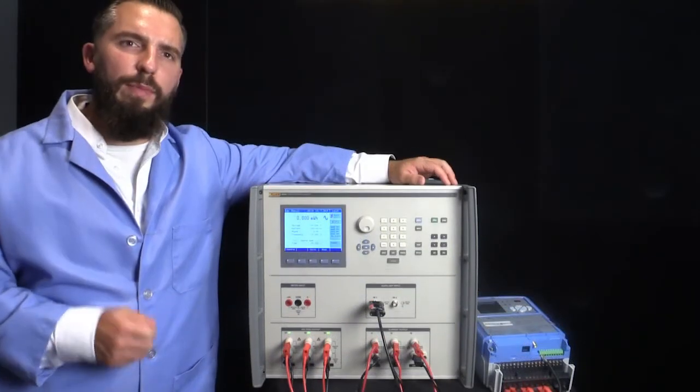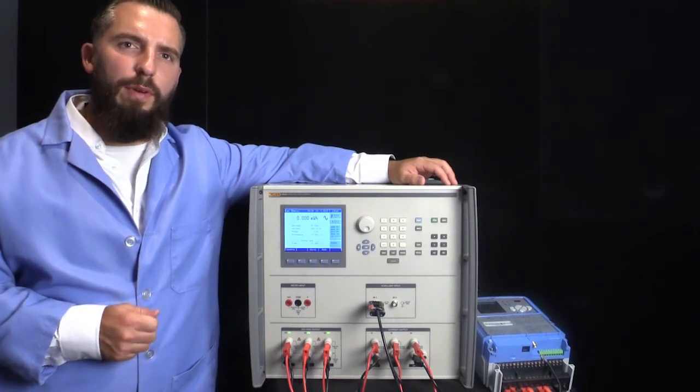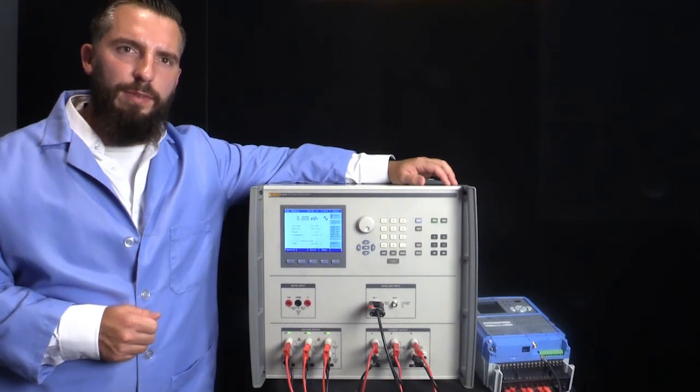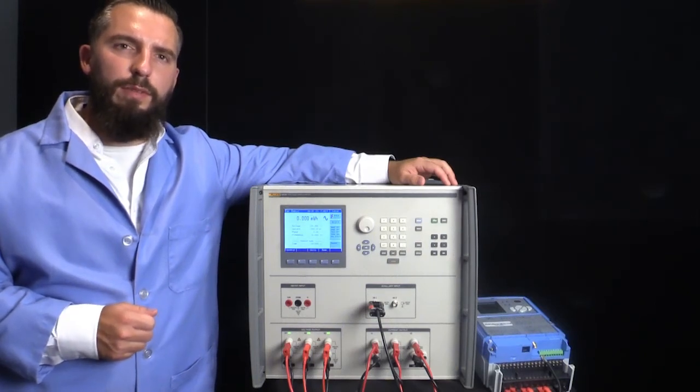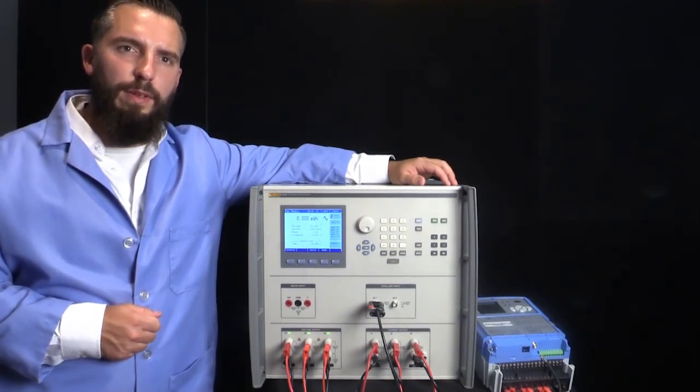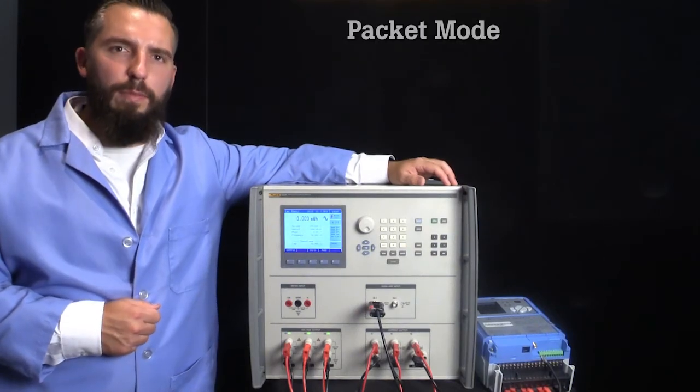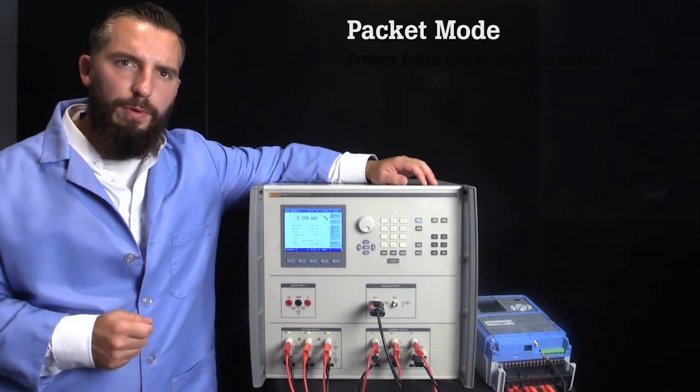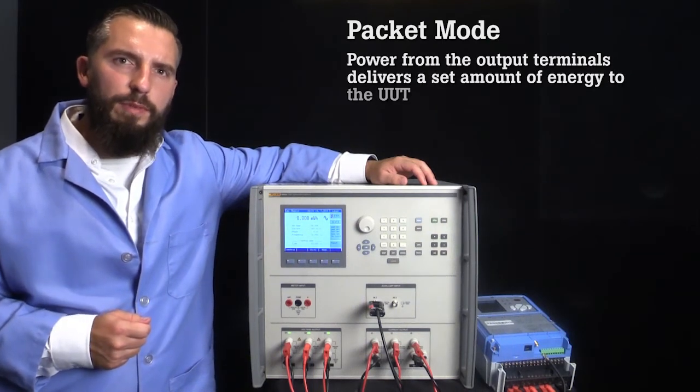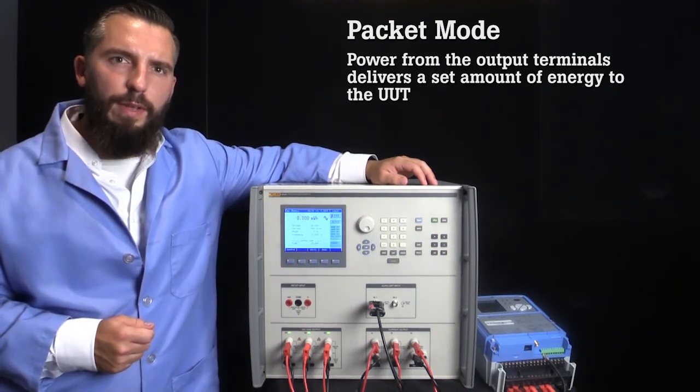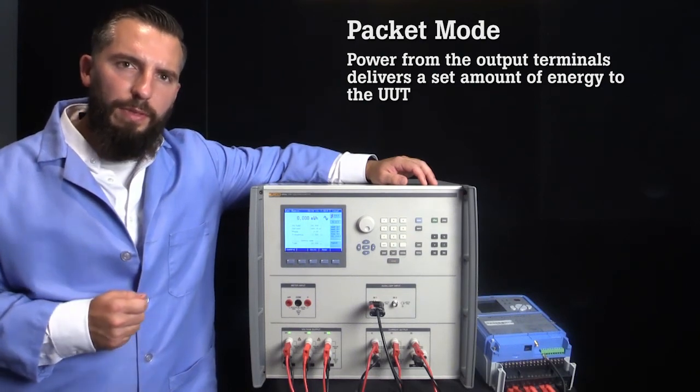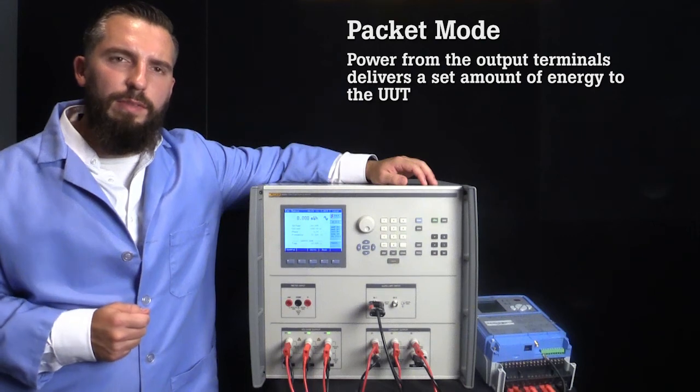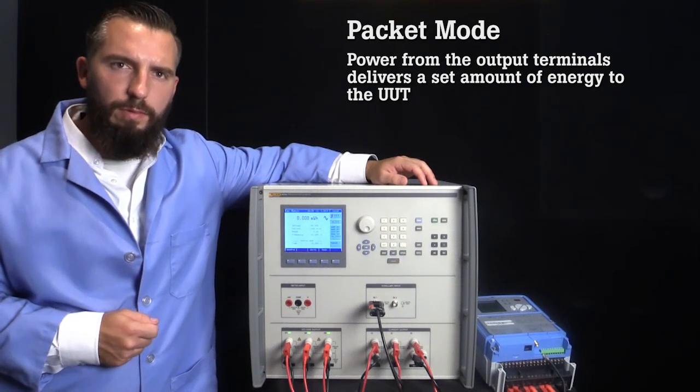In some cases, you may have to test an energy meter without a pulse output. In this case, the simplest method is to do a timed energy test where you compare the expected value to the measured value on the energy meter. This can be done using the packet mode. In packet mode, which is also known as dose mode, the power from the output terminals is timed to deliver a set amount of energy to the meter under test. This method is not as accurate as the other methods because the startup time of the 6003A is not synchronized with the UUT, but it is the simplest.